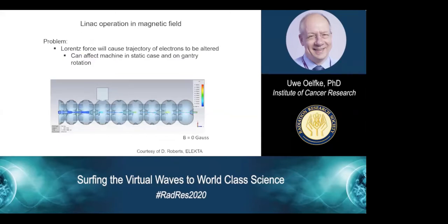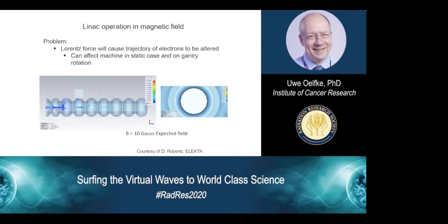Let's look at a simulation of the beam generation, for instance, in the waveguide. You see here that electrons are entering the waveguide with no magnetic field, and this device is trimmed and calibrated in such a way that you have a sufficient output to be used for radiotherapy later. However, if you switch the magnetic field on, you can see in this simulation that the Lorentz force causes the trajectories of the electrons to be altered, and this has a tremendous effect. You see these electrons are basically reflected in these cavities, and there's almost no output leaving the waveguide.